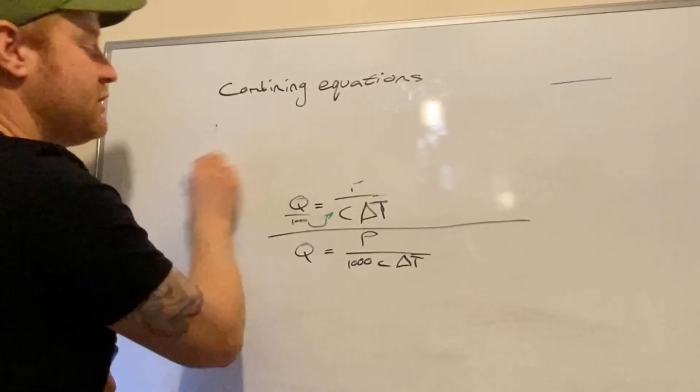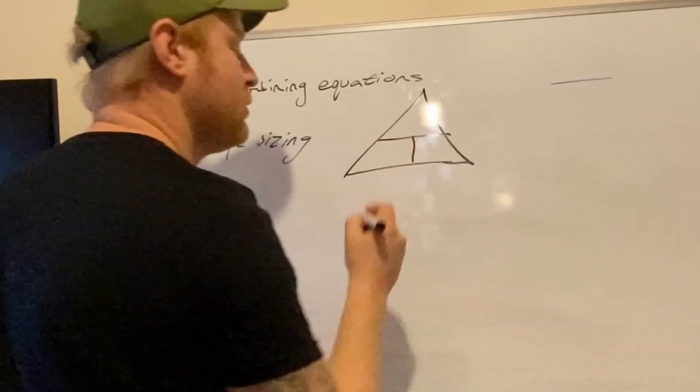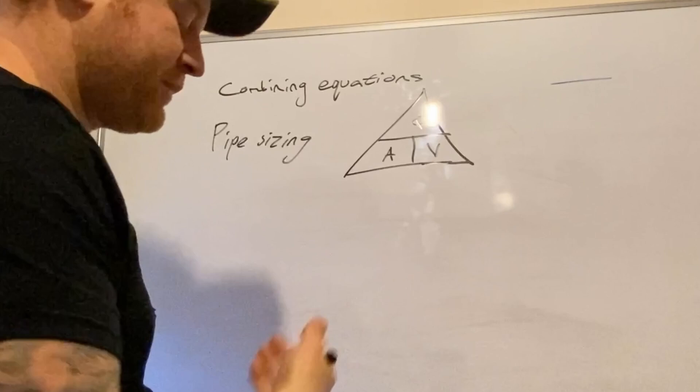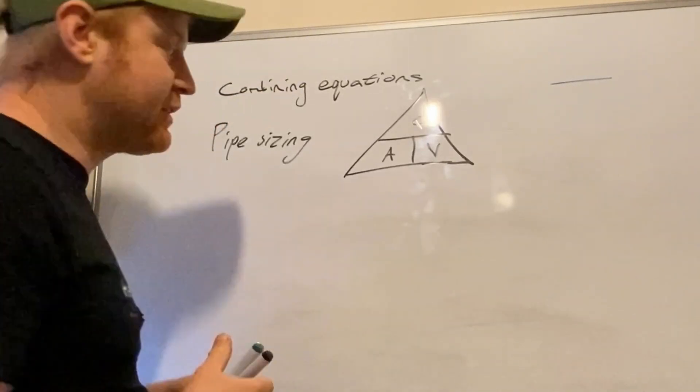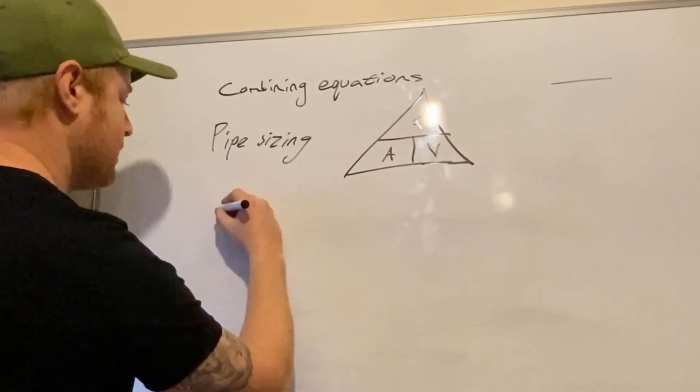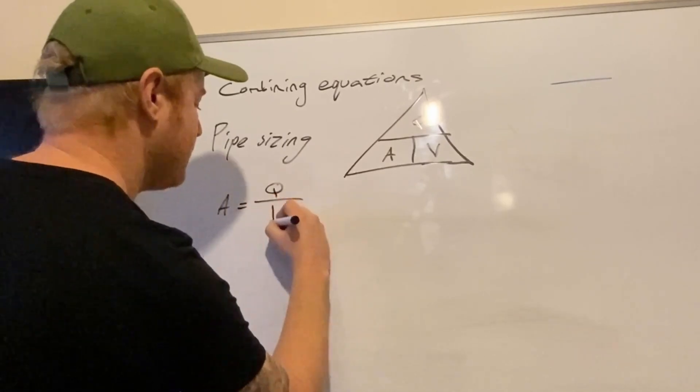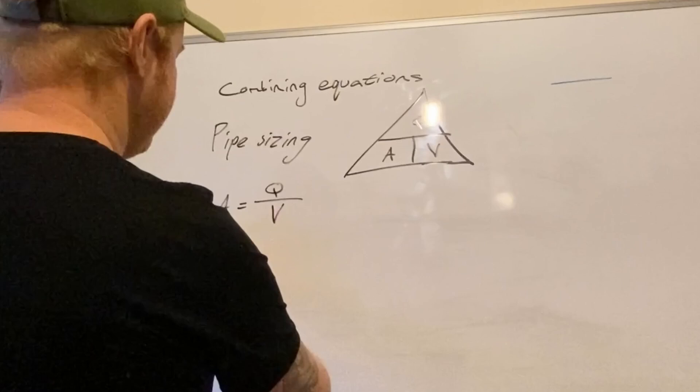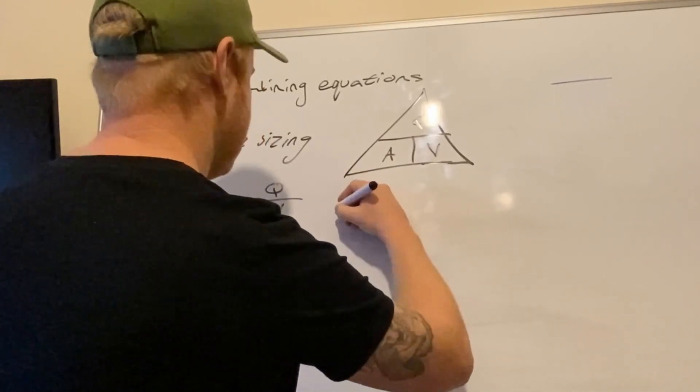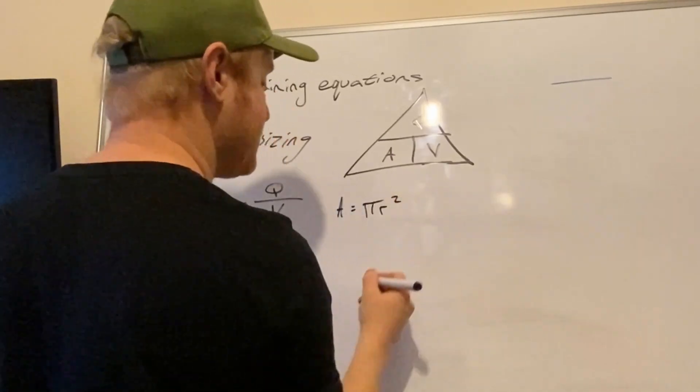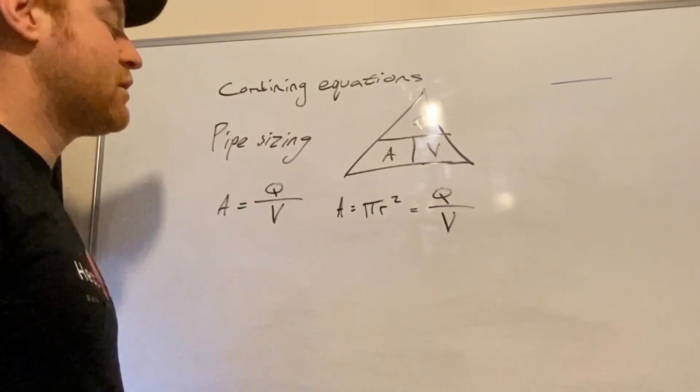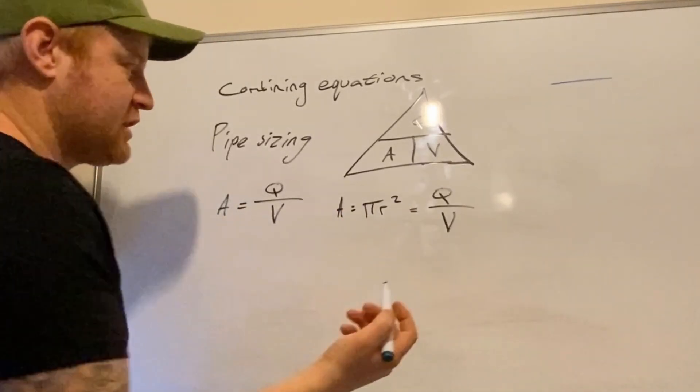The next one we do is pipe sizing. So we're all familiar with this triangle, which is the velocity triangle. Flow on the top, velocity on the bottom, area the result when we're working out the area. Area is not very useful for us. So if we break down the area... First of all, to write this longhand, area equals q over v velocity. But we don't really want area because area is pretty useless. So what is area? Area is π R squared and that is flow over velocity. But also, that's pretty useless for us as well, right? So we want to separate this out.